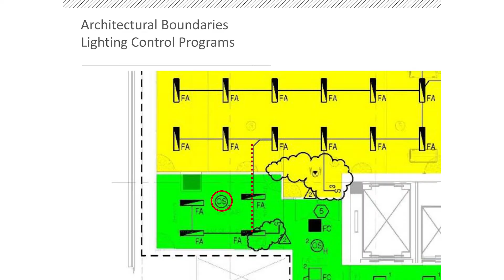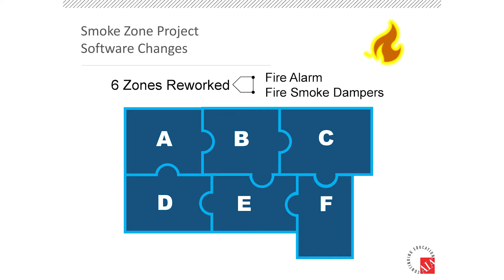This is a particular building that had a very much out-of-code-compliant fire alarm system. And so the project scope looked really simple on paper. Hey, it's an occupied building, but they've been out of code compliance, and the authority having jurisdiction happens to actually be the owner in this case. So they had these 6 zones where they're going to take the fire smoke dampers, rewire them all, take them off the building automation, and have them controlled by the fire alarm system.